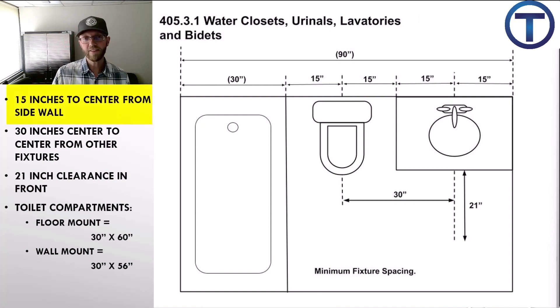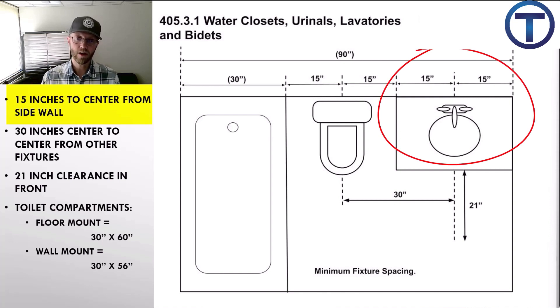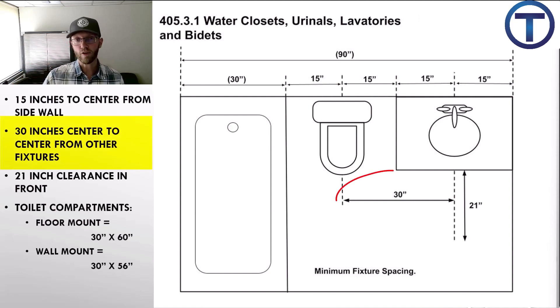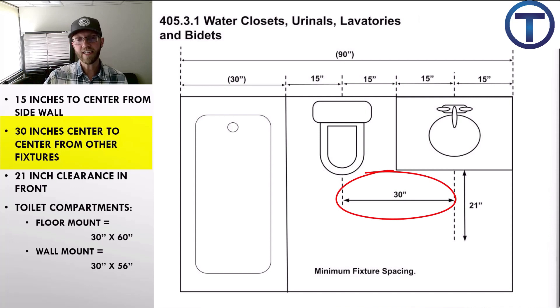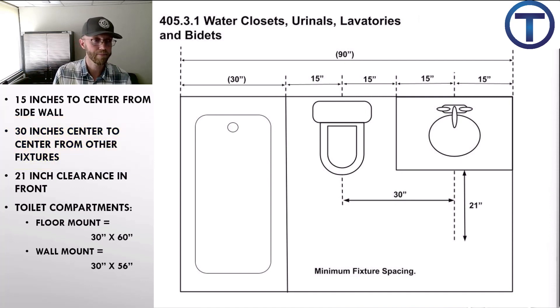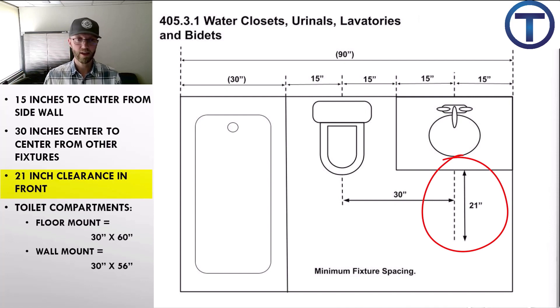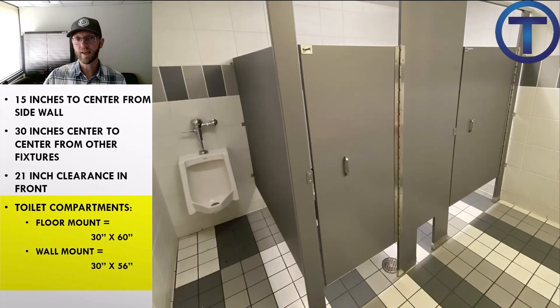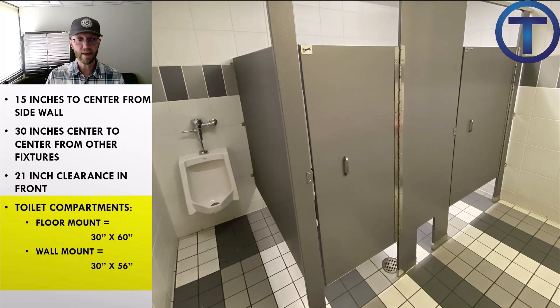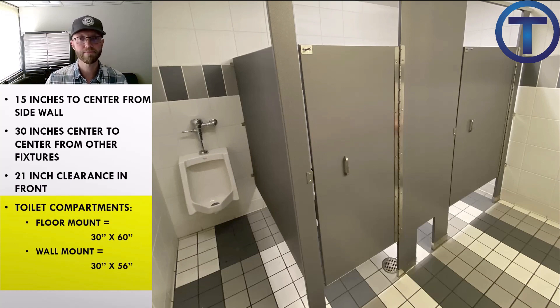Fixtures need to be 15 inches away from a sidewall to the center. You can see that with a lavatory. 30 inches center to center from other fixtures — 15 inches for one fixture, 15 inches for the next. We have to have a front clearance of 21 inches — that's where you can approach the fixture, the space out in front of the toilet. This also defines toilet compartments: the smallest a floor-mounted compartment can be is 30 by 60 inches, and a wall-mount toilet compartment is 30 by 56 inches.